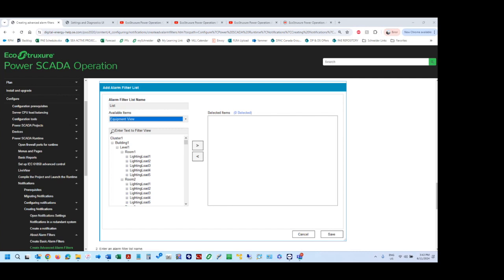The other way could be using a code function, but I don't know how to do that off the top of my head. An alarm in my world is a value above, say, 128 to 255 or something like that. Priority. So that automatically constitutes an alarm, and it should come into the alarm and notification, and then we should be able to enable that through the system. So I'll have to take that off and get you that. Let's say, what would be the criteria, below 0.9? Right now we're set to 0.88. For 30 minutes. And for 30 minutes. Okay.